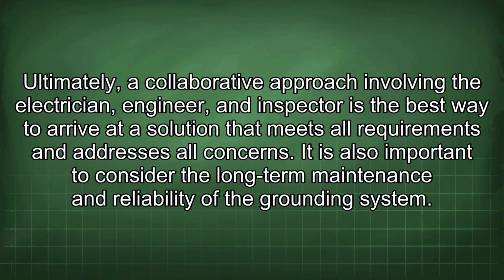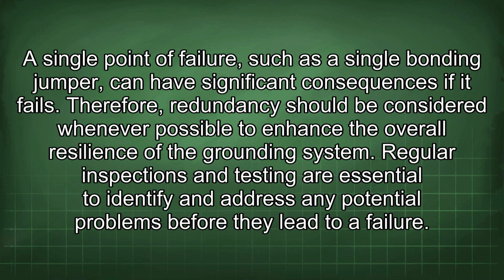Ultimately, a collaborative approach involving the electrician, engineer, and inspector is the best way to arrive at a solution that meets all requirements and addresses all concerns. It is also important to consider the long-term maintenance and reliability of the grounding system. A single point of failure, such as a single bonding jumper, can have significant consequences if it fails. Therefore, redundancy should be considered whenever possible to enhance the overall resilience of the grounding system. Regular inspections and testing are essential to identify and address any potential problems before they lead to a failure.